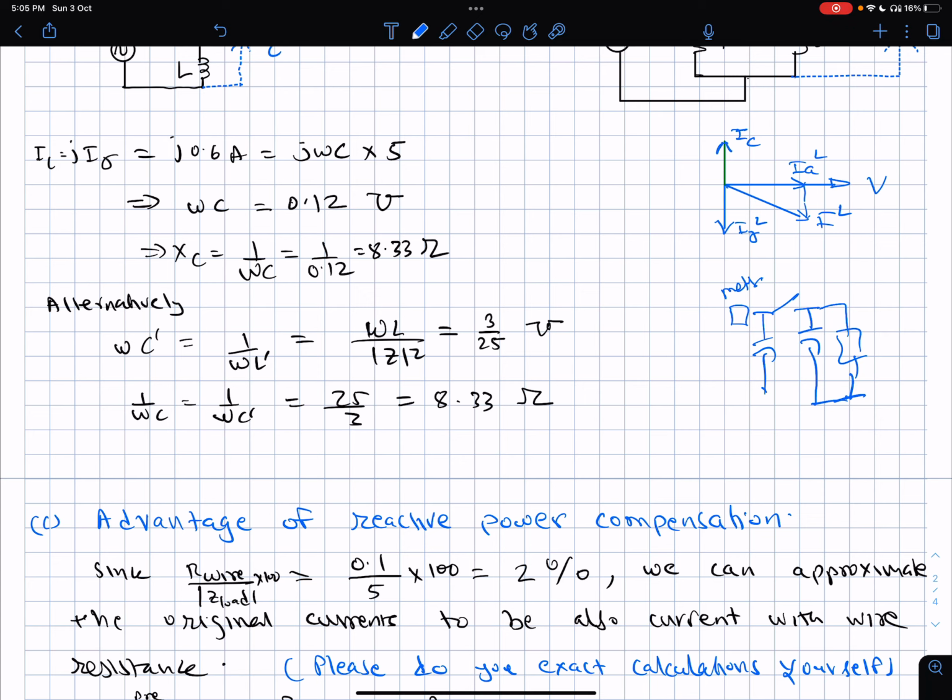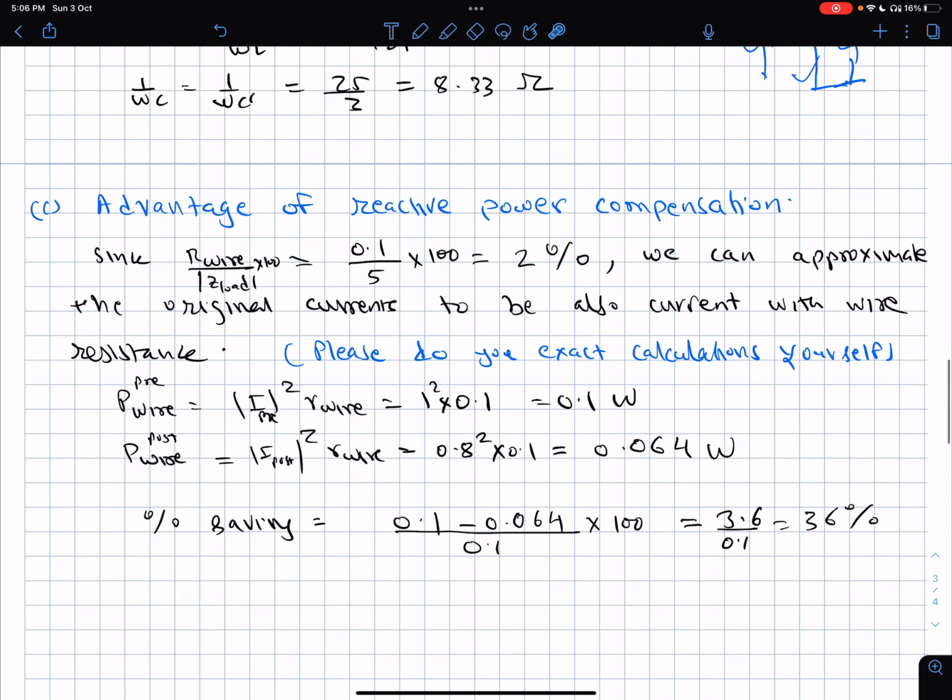What is the power factor of the capacitor? 0, leading. So your power factor would have again got deteriorated, and you would unnecessarily, under no load condition, when there is no load also, continue to draw reactive power. So the positioning should also be at the load end, a shunt device connected such that when the load is disconnected, along with it the capacitor is also disconnected.